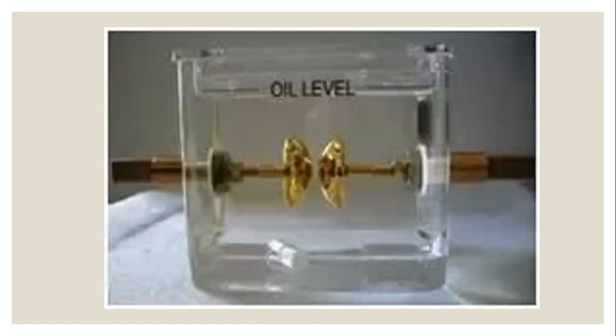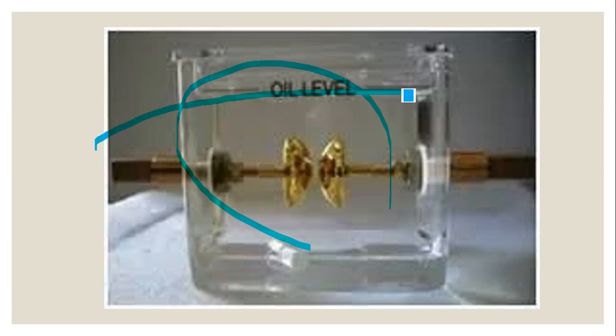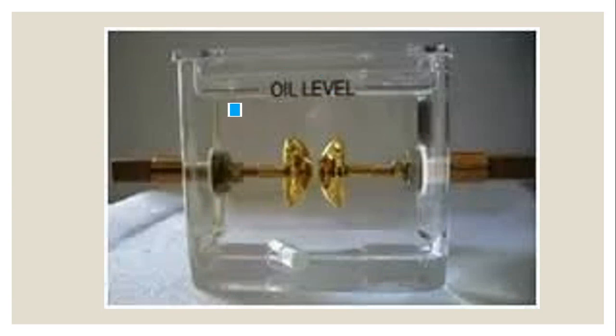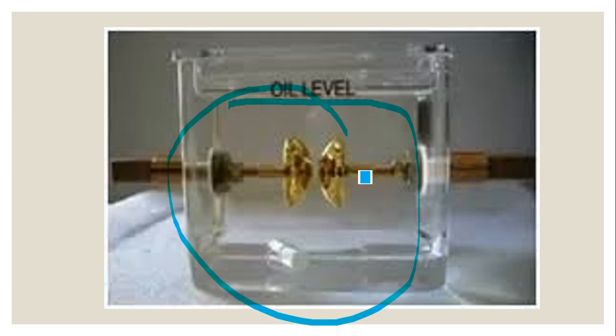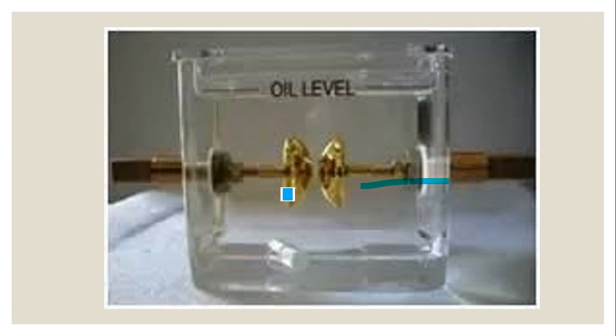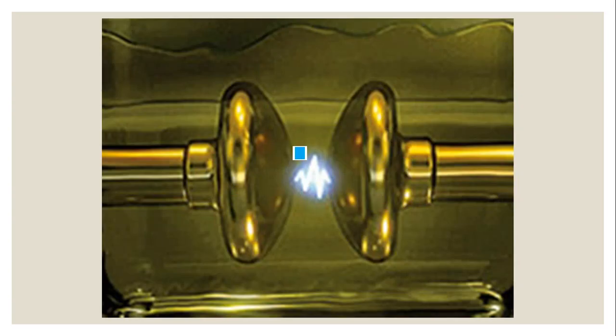We will now see its condition. This is the testing chamber, and the oil has to be filled up to the oil level. After filling the oil, we will increase the voltage, the breakdown voltage, between the two electrodes at both ends. At a particular point of time there will be a flash.